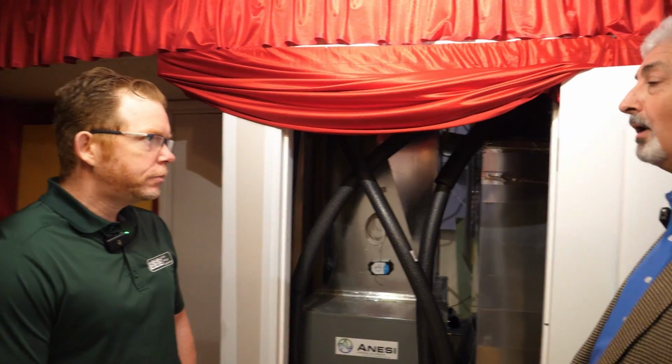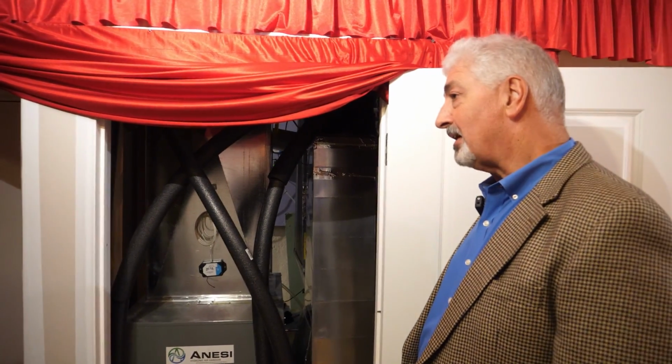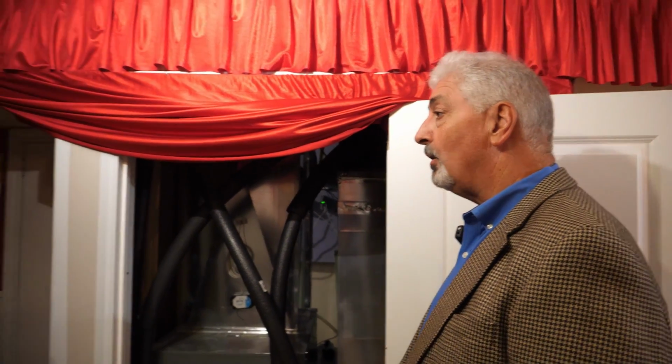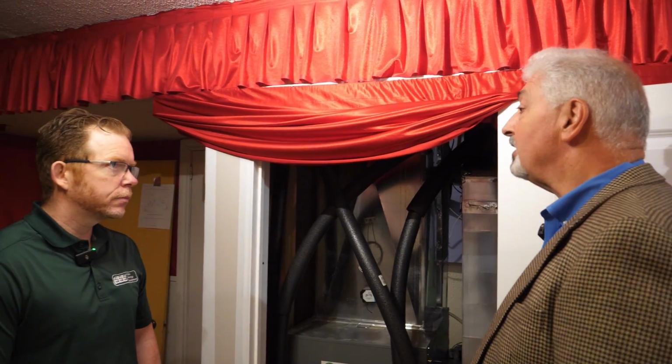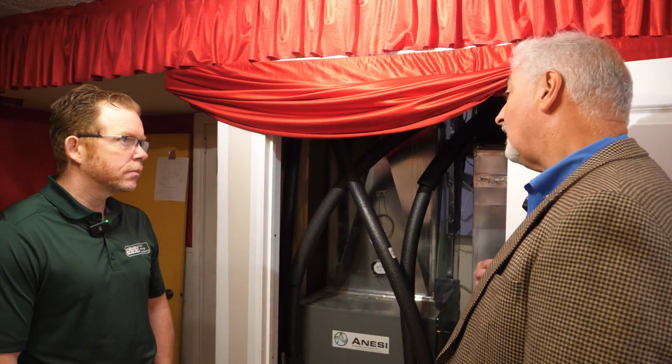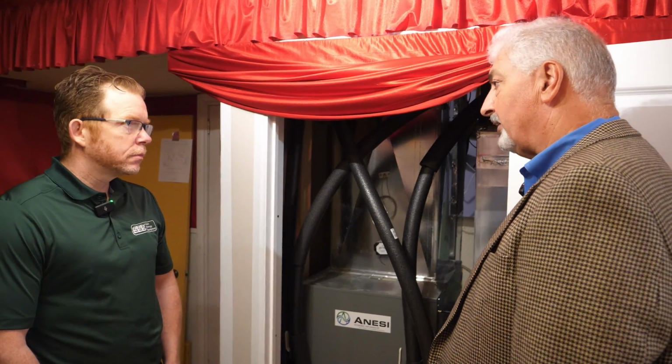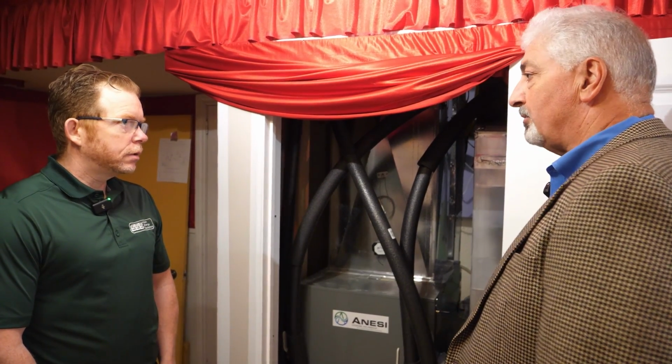Okay. Like I said before, we prefer to have the indirect tank that we've spec'd out. It's got a 20-degree copper coil. Now, you don't have to use our tank, and you don't even have to use an indirect storage tank. We could use a standard storage tank with a plate heat exchanger. Yeah. So if the application requires something outside of the amount of heat exchange space on the coil, we can certainly look at an external plate heat exchanger to accomplish that.